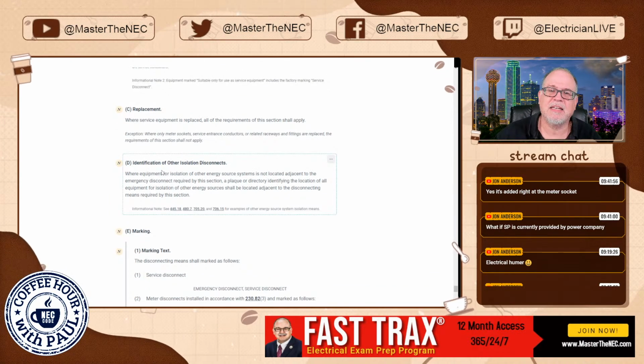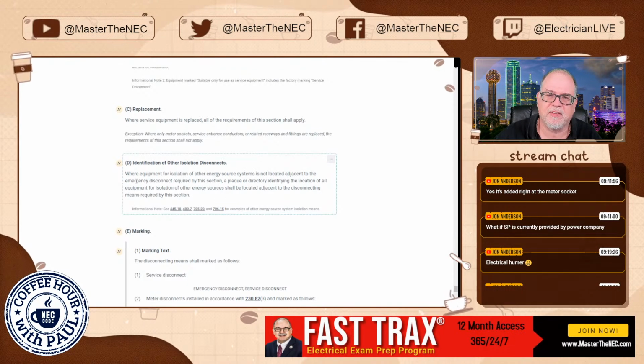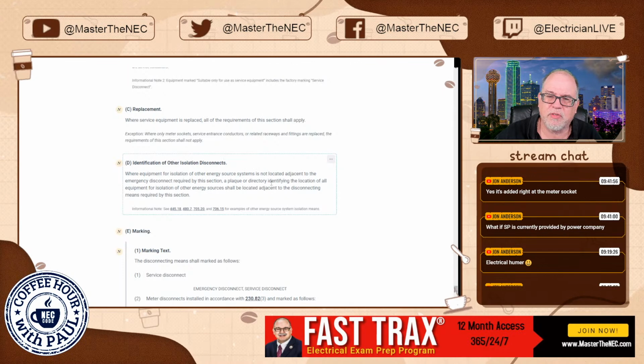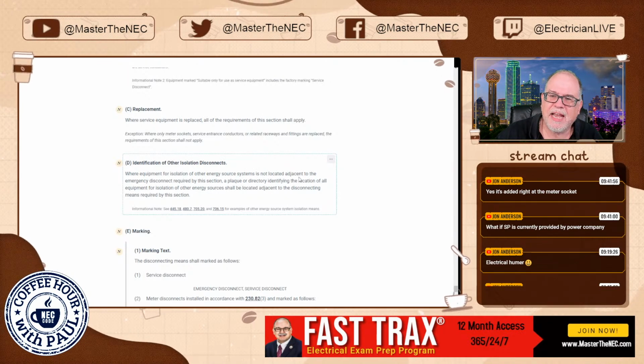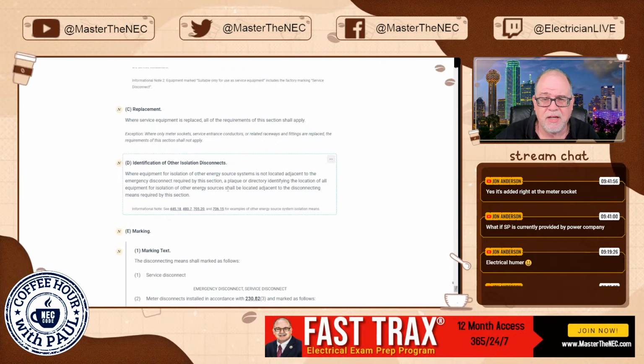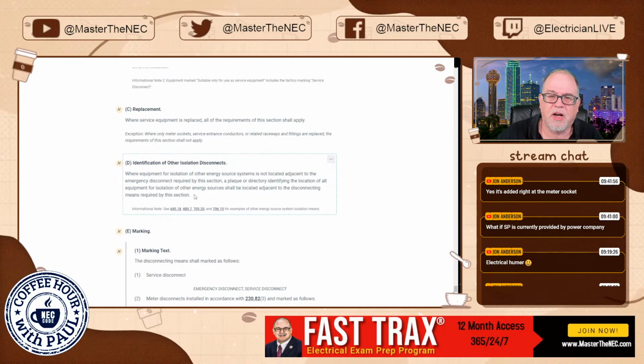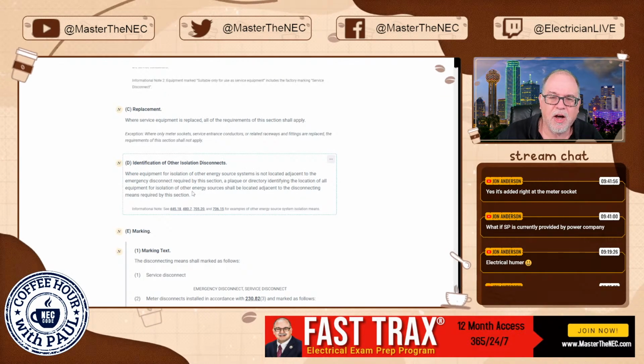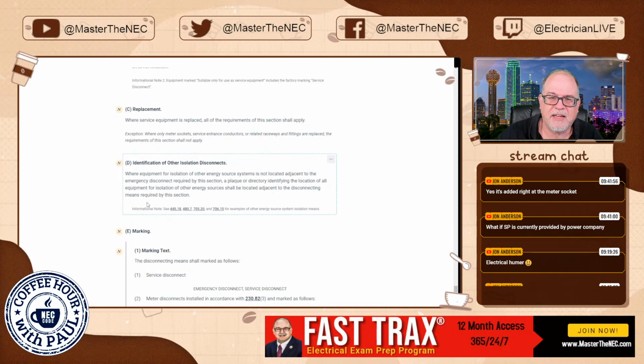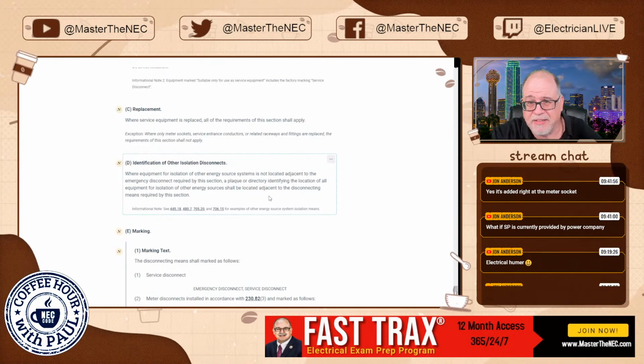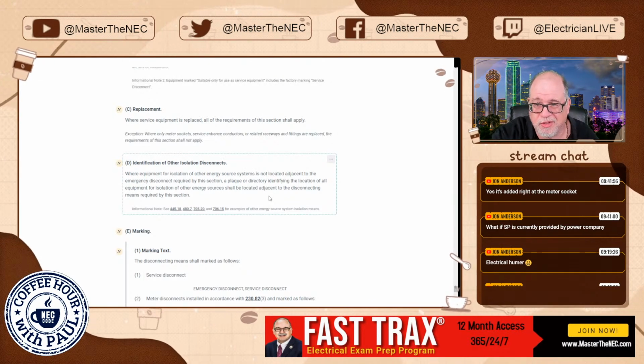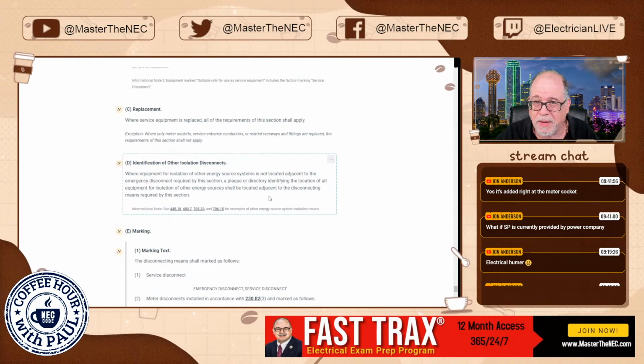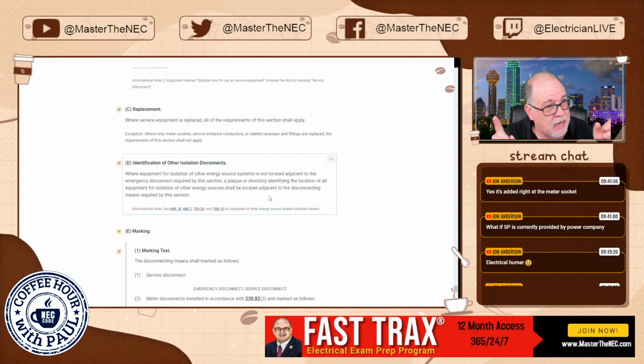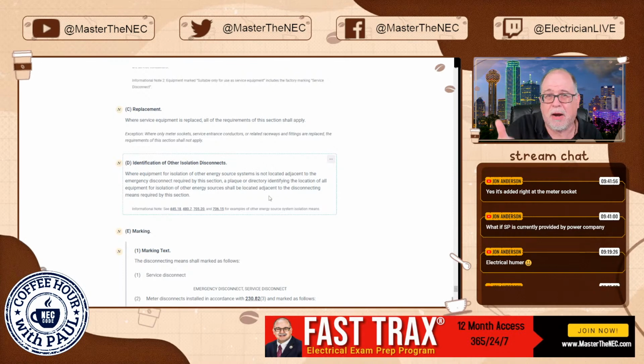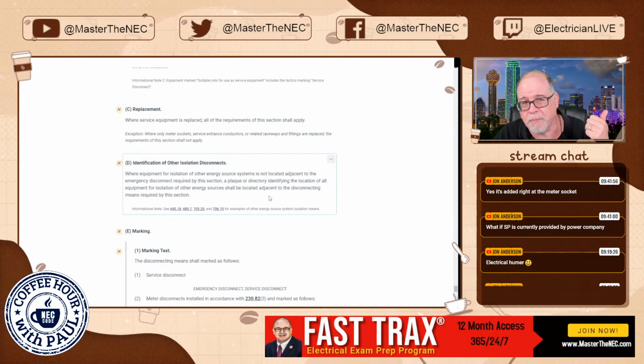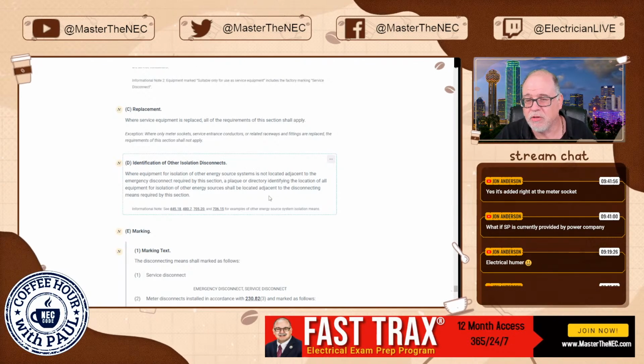And here it says identification of other isolation disconnects. It says where equipment for isolation of other energy sources like PV, wind generation, and whatnot is not located adjacent to the emergency disconnect required by this section, a plaque or directory identifying the location of all equipment for isolation of other energy sources shall be located adjacent to the disconnecting means required by this section. Hey, if I've got other disconnects somewhere else based on other systems that are being brought to this dwelling, you can bet your bottom dollar that at this emergency disconnect location, I want to know where they're at. It kind of defeats the purpose if I'm killing power to this dwelling unit, and then I've got other sources of power that are feeding the dwelling unit. Not good. So again, makes sense, right?